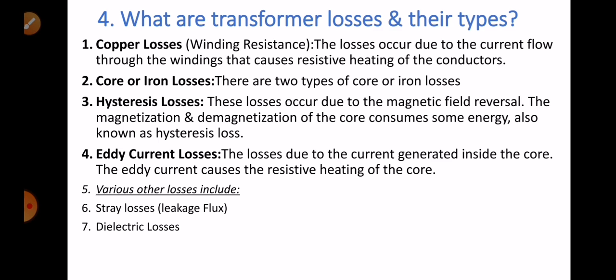Loss number two: core or iron losses. There are two types of core losses. Number one is hysteresis losses — these occur due to magnetic field reversal; the magnetization or demagnetization of the core consumes some energy. Number two is eddy current losses — these are due to currents generated inside the core. The eddy current causes resistive heating of the core. Eddy current is an undesired current which flows opposite to the actual flow, creating heat.